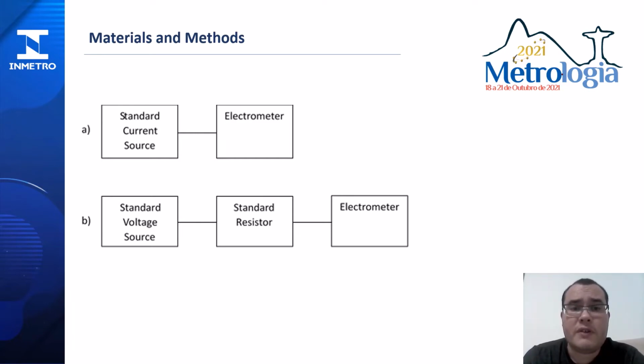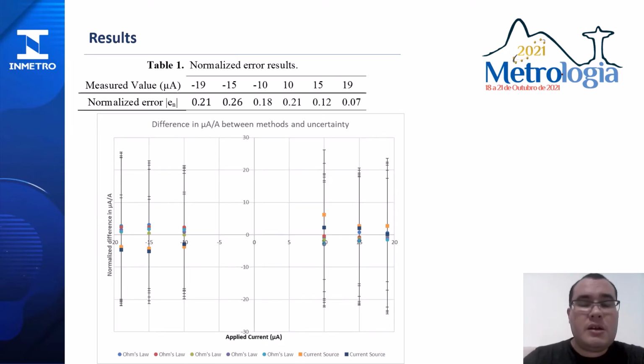A software was developed to make this calibration, and the details are presented in a second paper called A Software to Calibrate Low Current Meters in the Range of Picoamperes to Microamperes. The values compared were 10, 15, and 19 microamperes in the forward and reverse directions. The normalized error between measurements was less than 1 for all points, showing that the results were satisfactory and that the calibration system can be validated.